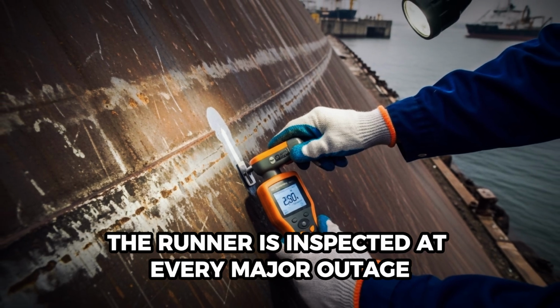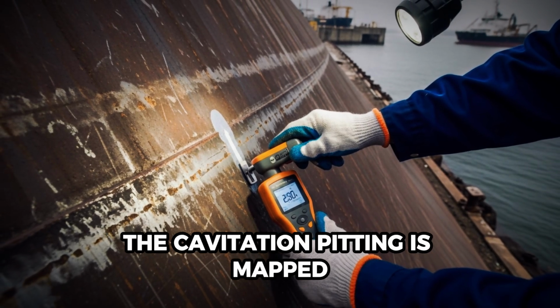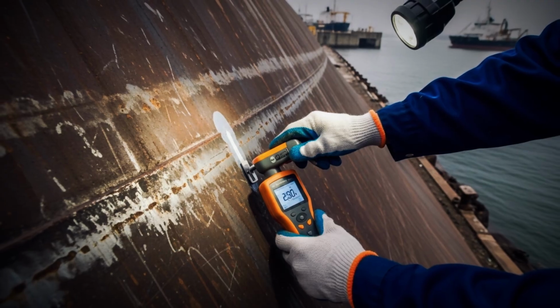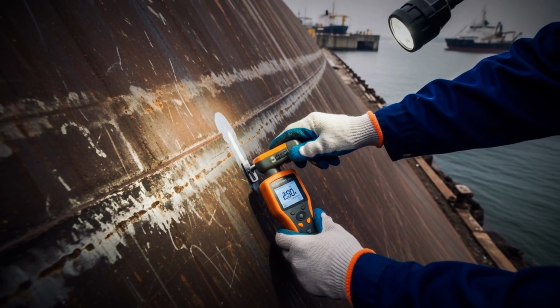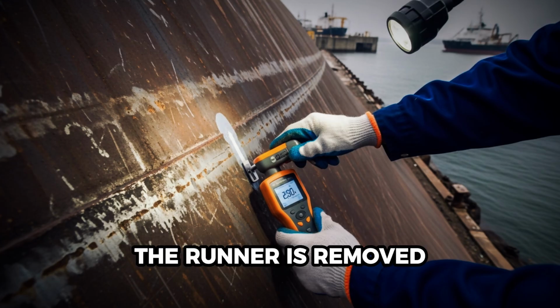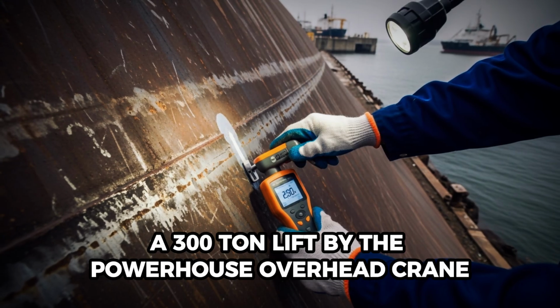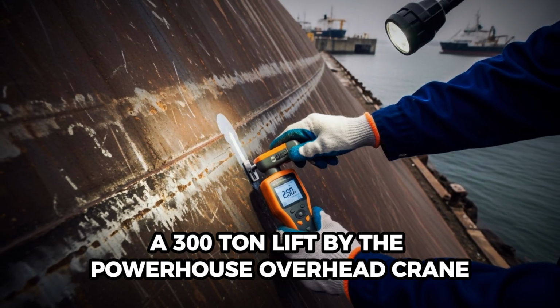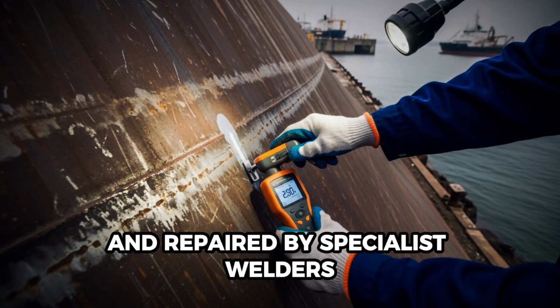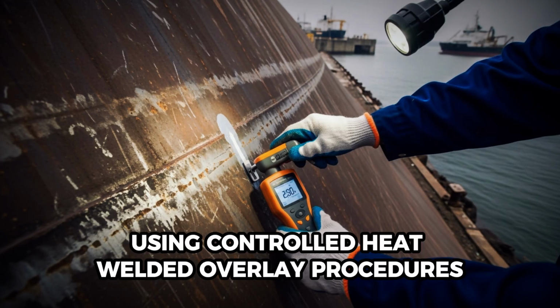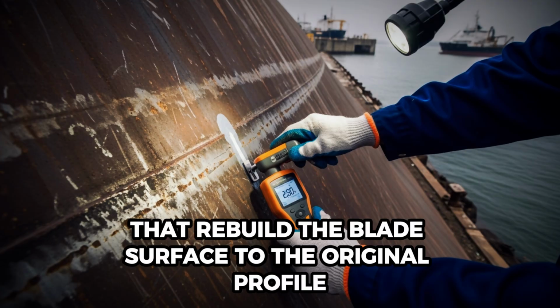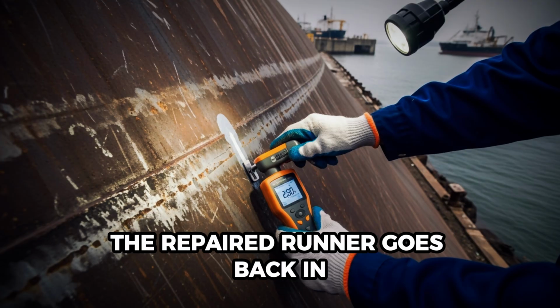The runner is inspected at every major outage. The cavitation pitting is mapped. The erosion rate is tracked. When the pitting exceeds tolerance, the runner is removed. A 300-ton lift by the powerhouse overhead crane, and repaired by specialist welders using controlled heat weld overlay procedures that rebuild the blade surface to the original profile. The repaired runner goes back in.